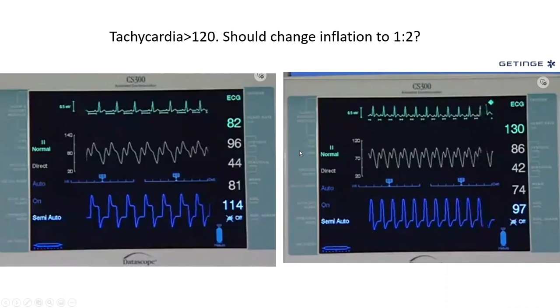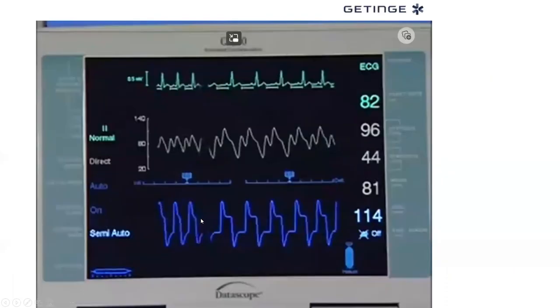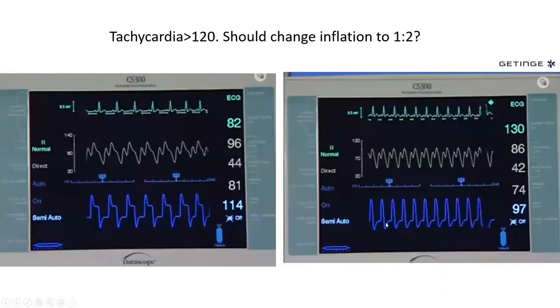Helium gas is light and has very fast transfer and fill time. So it's not that if you're shrinking diastole, the gas will not have time to fill the balloon. No, it will have time to fill the balloon. And indeed, you can see the height of that waveform has not changed when you change the rate. So the balloon fills instantaneously. So changing to 1 to 2 is not going to improve augmentation. You will just get augmentation less often, which is worse for the patient. But tachycardia does worsen augmentation.